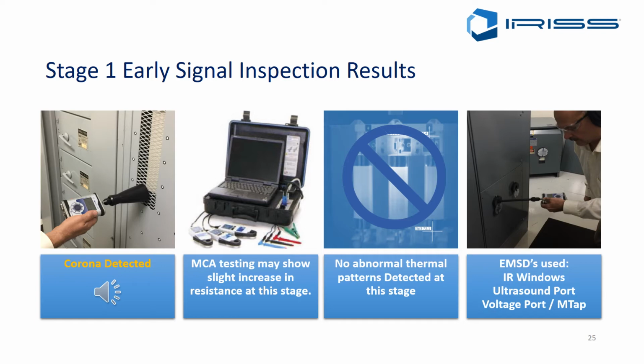Your motor current analysis may start to show slight increases in the resistance measurements at this stage. There should be no abnormal thermal patterns detected. But all the time we're doing this utilizing EMSDs, electrical maintenance safety devices, such as IR windows, ultrasound ports, and voltage tap-off ports. The panel stays closed and guarded all the time. It's a very quick and easy inspection done under full load condition.